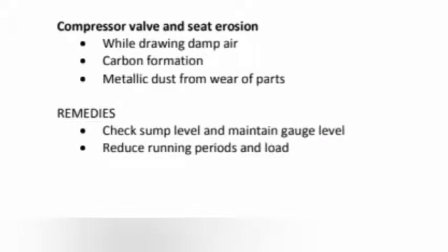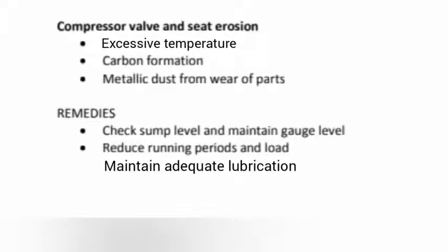Compressor valve and seat erosion. Possible causes: number 1, while drawing damp air, there may be carbon formation. Number 2, metallic dust from wear of parts. Possible remedies: number 1, check sump level and maintain gauge level. Number 2, reduce running periods and load on the compressor.